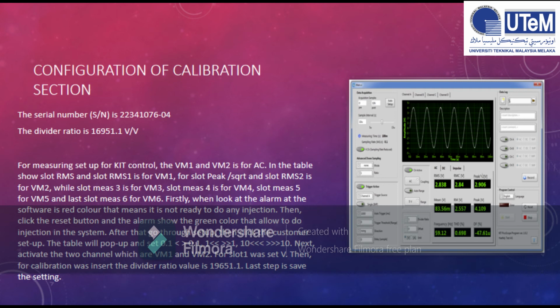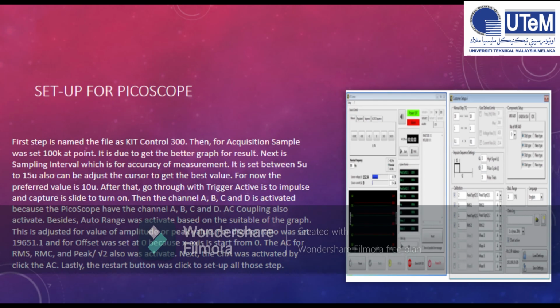Next is activate the 2 channel which are VM1 and VM2. For slot 1 was set V, then for calibration was insert the divider ratio value, which is 19651.1. Last step is save the setting. Last for section 2 is about setup for picoscope.